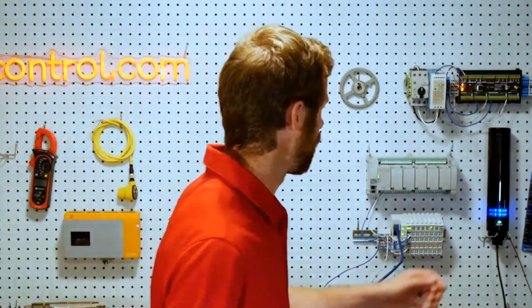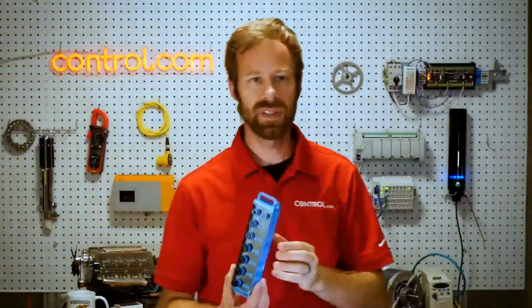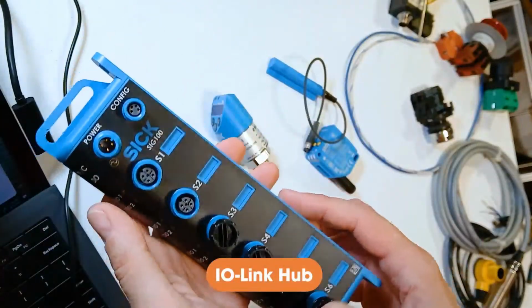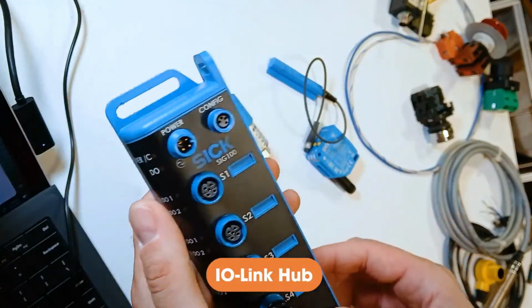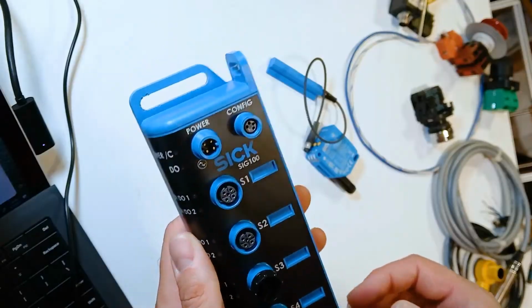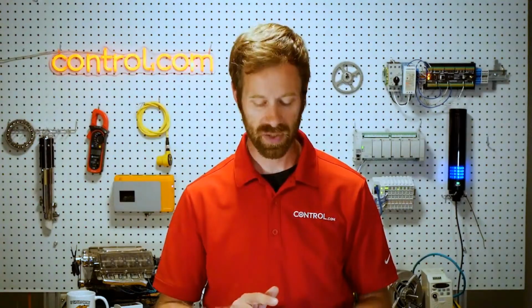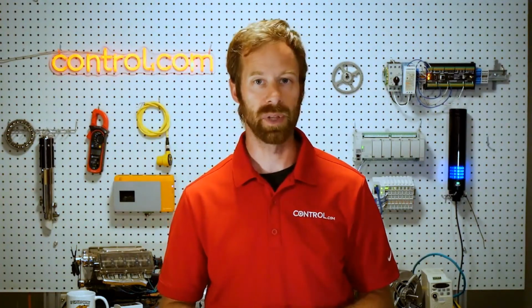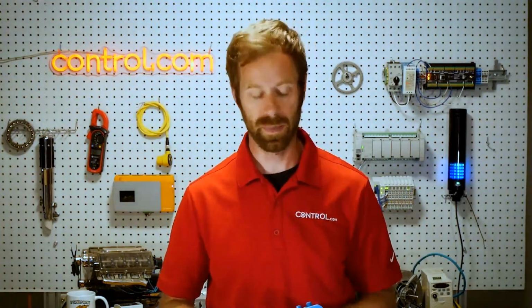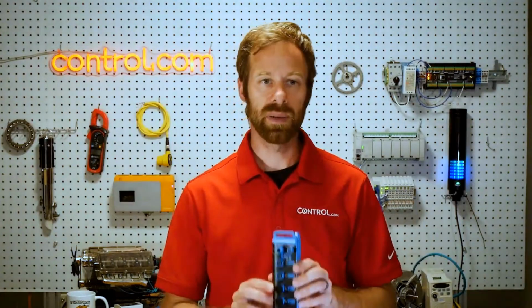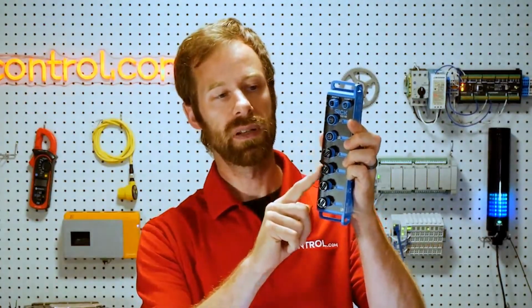Well, right behind me on the wall, I have an example of a device. This device is called an IO-Link hub or master device. This one's actually programmable to be able to accomplish quite a few different tasks, but usually what we're interested in is a device that they refer to as a master device, which connects to a PLC through a field bus communication like Ethernet, Profinet, something like that. And then each one of the sensor connection pins can be either digital inputs or outputs or IO-Link data, which can send information out or in.